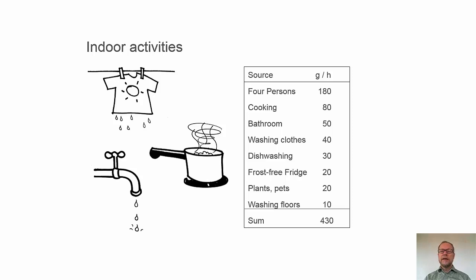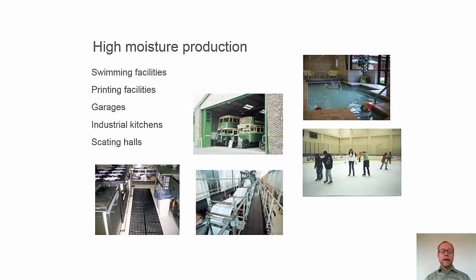And here, on the table here, we have some values, how much water vapor we are producing, like 4 persons could produce 180 g during an hour, cooking 80 g per hour, and so on. If we sum it up, we can very easily get 430 g per hour.